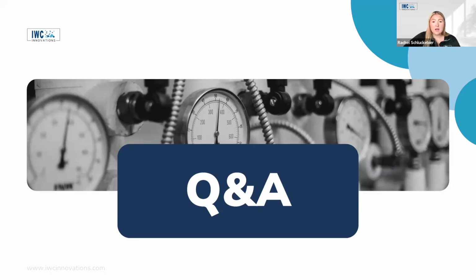We got another question: how do you identify low-used outlets and faucets? That's when you have to bring in the team, right? That's why you can't just have one person in charge of managing the water safety of the building, because they might not have access to that information. If it's a healthcare space and you have building occupancy records, just monitor if there's not a resident in a room for a week or two, and assume that outlet's not being used. You can also learn about them by testing the residual disinfectant at distal points throughout your building. If you go up to an outlet and test it, and it's not the right temperature and it's not the right disinfectant level, but the outlets down the hall are in the range that you want, that probably means there's some stale water in that outlet and it needs to be flushed.